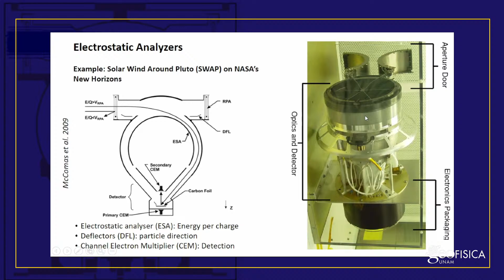To give you an idea of the size, from top to bottom it's around 20-25 centimeters. So let me now take a cut through this instrument and make the 2D diagram to explain the measurement principle. So you see the positively charged particle will come from the left in this case. And here in the aperture, we have the retarding potential analyzer. It's not really important for the scope of this talk, but since it's there, let me just say. So you can apply a potential difference between these two grids, and then the particles that don't have enough energy per charge to overcome this voltage difference will get deflected and get rejected from the instrument. While those that have enough energy will overcome the potential barrier and continue through the instrument.